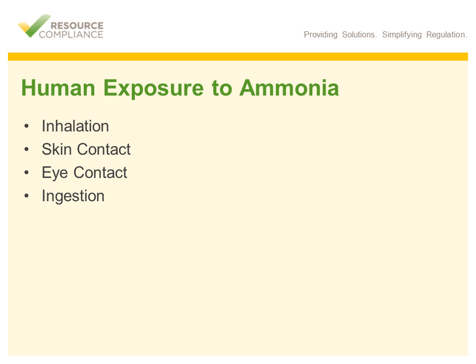Inhalation is the most common method of ammonia exposure. Inhalation of ammonia gas causes sore throat, coughing, shortness of breath, and labored breathing. Anytime concentrations are expected to exceed 35 ppm, respirators should be used to prevent ammonia inhalation. Skin contact with ammonia gas or liquid can result in irritation and burns. Keep in mind that ammonia used in refrigeration systems is often very cold, so frostbite can also occur in conjunction with skin contact. Eye contact with ammonia is very serious and can cause irritation and permanent loss of sight or blindness. Ingestion is the least common form of ammonia exposure and will cause severe pain and burning to the mouth and esophagus.